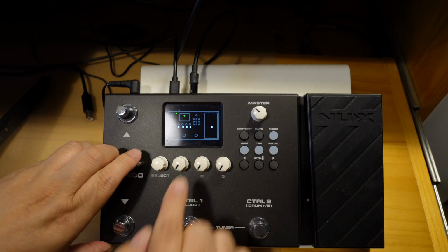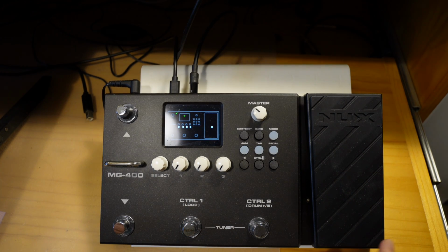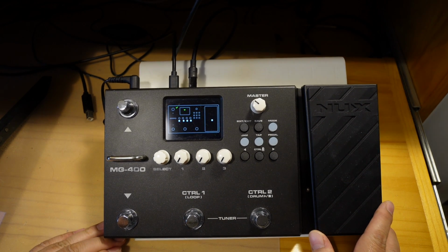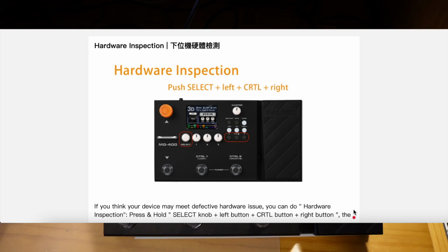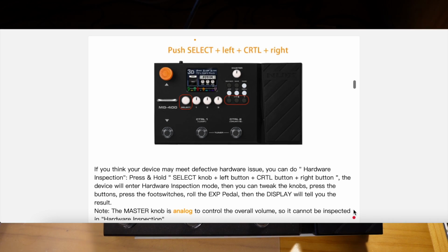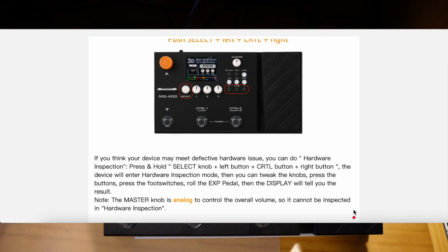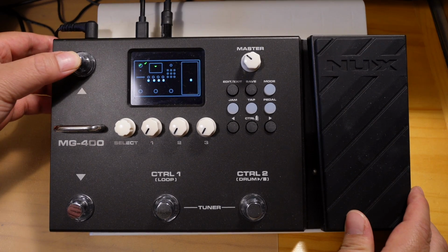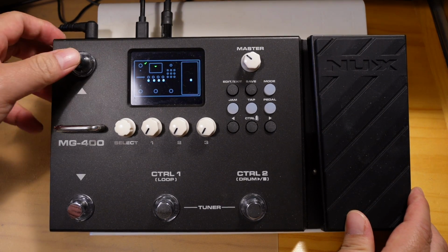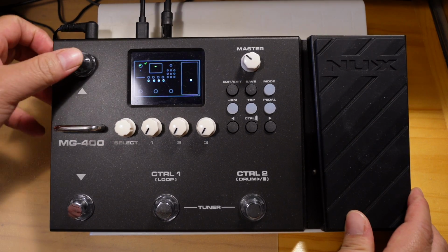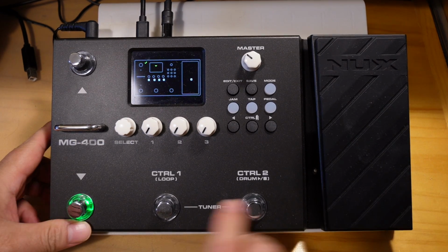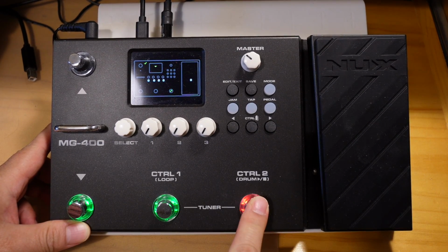As you can see, right now the device enters hardware inspection mode. You can check all the hardware. For example, right now I press the up foot switch, and you can see it shows on the display, and the down foot switch, and control 1 foot switch, control 2 foot switch.